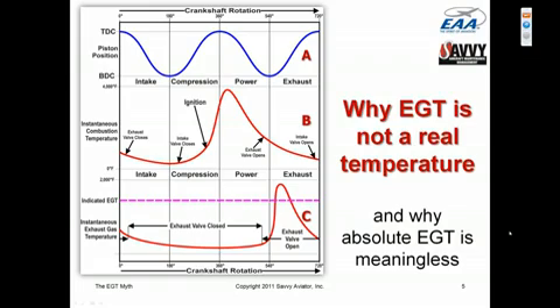So now, what exactly is the temperature that this EGT probe is reporting back to the gauge? Well, it's not the temperature of the exhaust gas. It's the temperature of the EGT probe itself. And what is that temperature? Well, the EGT probe, which has a fairly significant amount of thermal mass, is looking at all of these pulses of very hot gas, punctuated by long periods of nothing at all, and trying to somehow integrate all of that rapidly moving stuff into a probe temperature, which is actually a pretty arbitrary number. It's really not the exhaust gas temperature. Well, I guess it's the exhaust gas temperature at two instants of time. It's kind of like a stopped clock being right twice a day. But in no sense is the EGT value that probe reports back any kind of meaningful gas temperature.